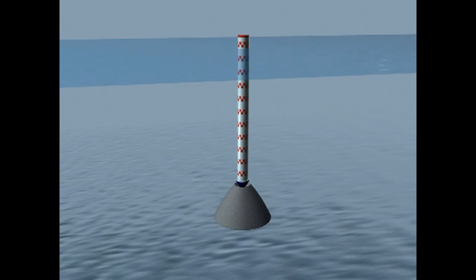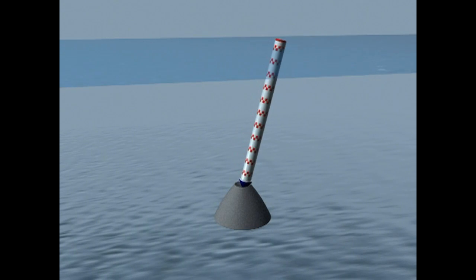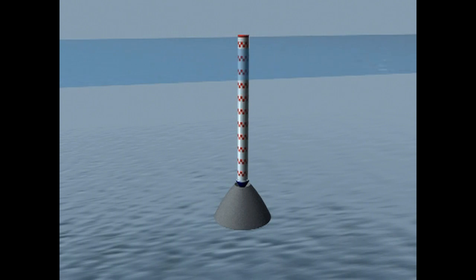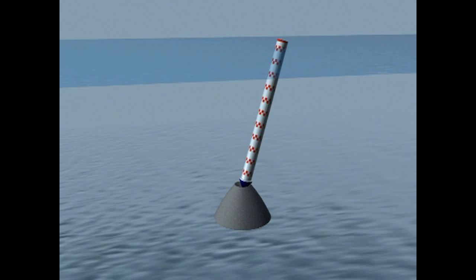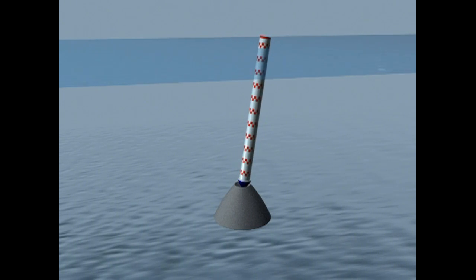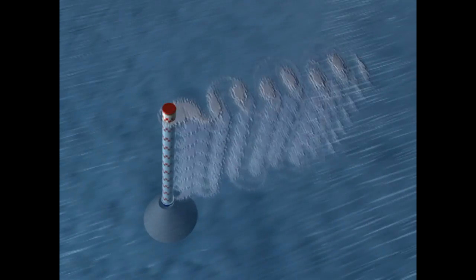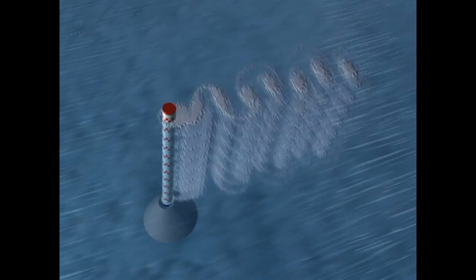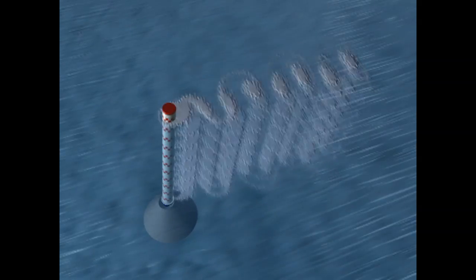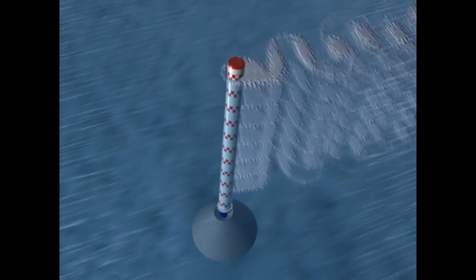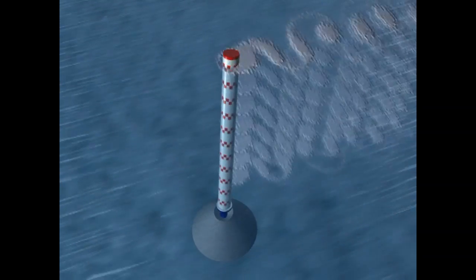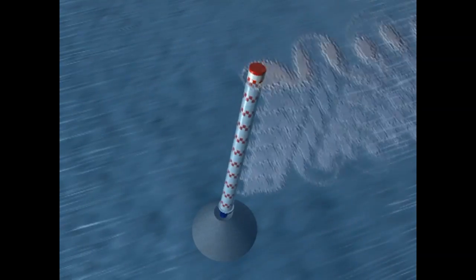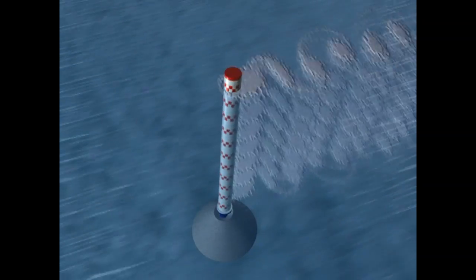The cylindrical float is anchored in the flow, free to rotate around its axis. The flow pushes the float over at an angle. The float buoyancy attempts to move it upright in opposition to the flow. The flow past the cylindrical float produces alternating low pressure areas downstream, in an effect called vortex shedding, which moves the float from side to side. This combination of forces produces a continuous figure 8 type movement in the float.